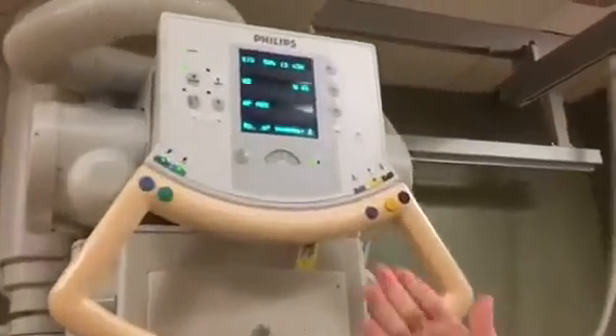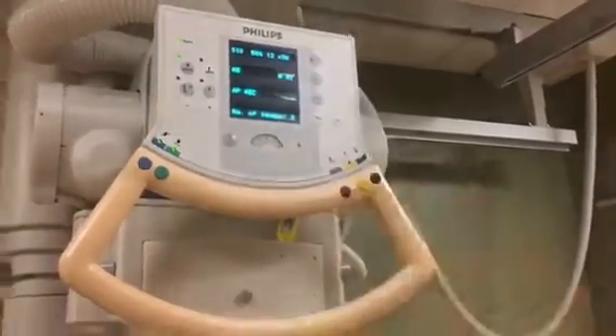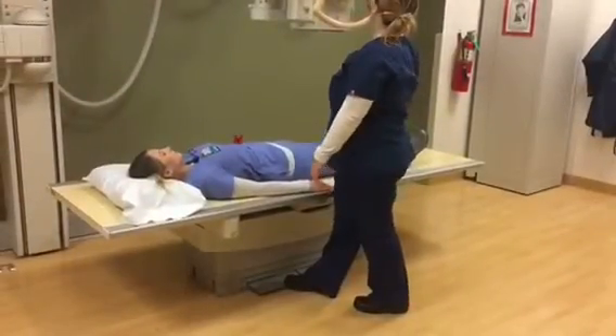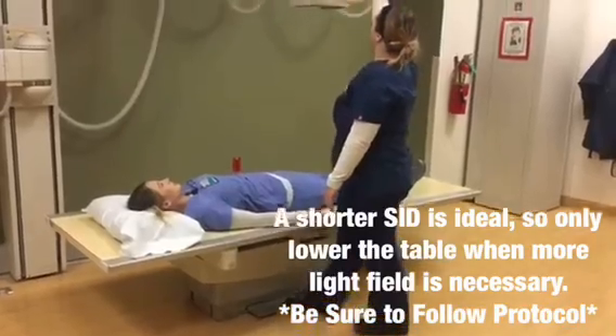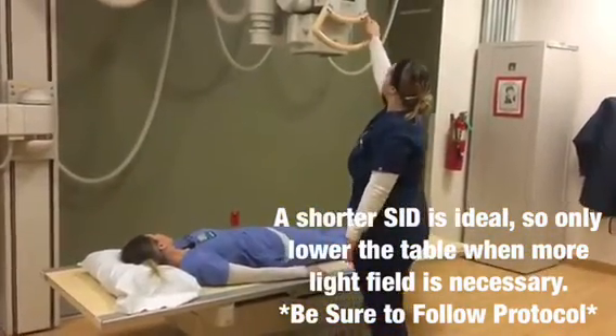I know that it's ready for stitching because it says number of images 2. Some systems require that the table be lowered all the way and the tube head be raised all the way up to allow for stitching.